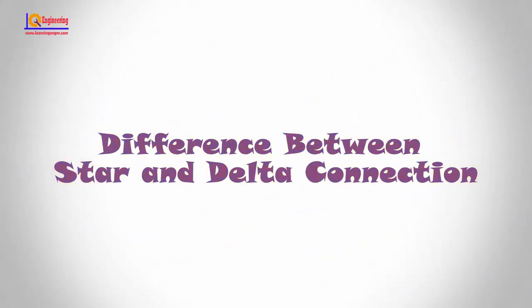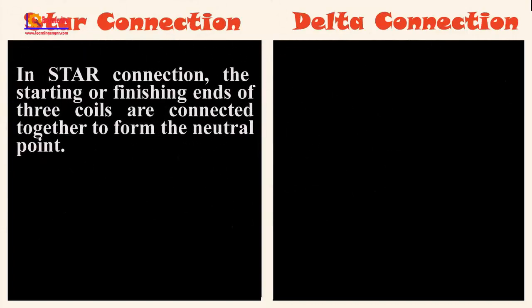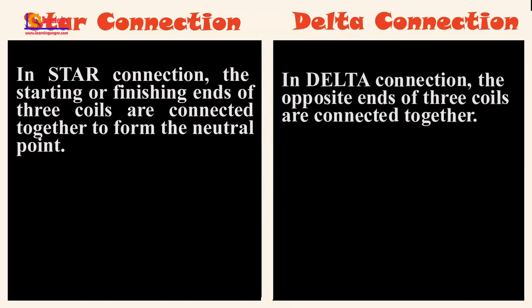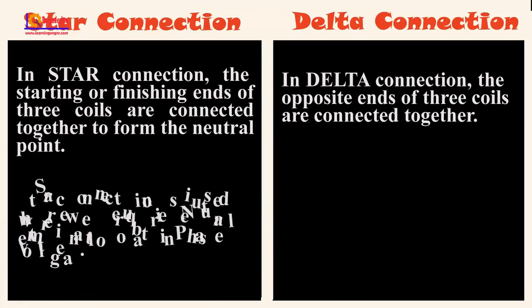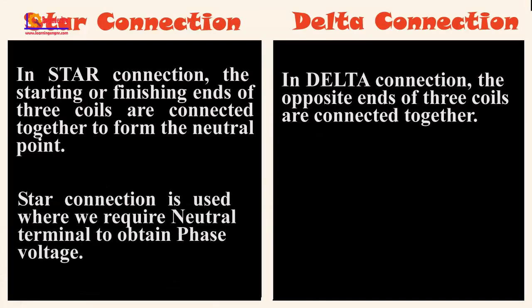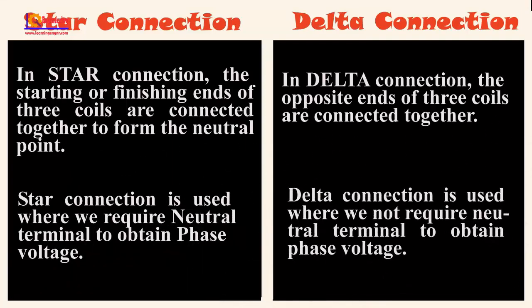In star connection, the starting or finishing ends of three coils are connected together to form the neutral point. In delta connection, the opposite ends of three coils are connected together. Star connection is used where we require a neutral terminal to obtain phase voltage; delta connection is used where we do not require a neutral terminal to obtain phase voltage.